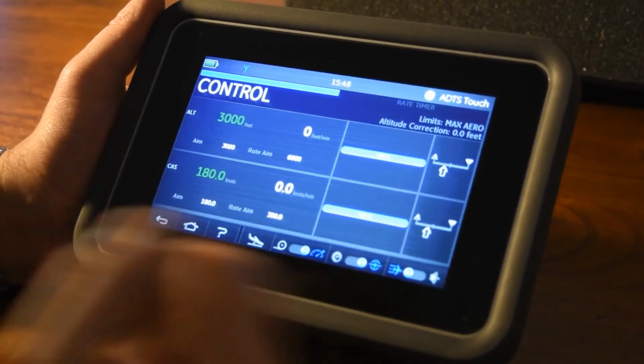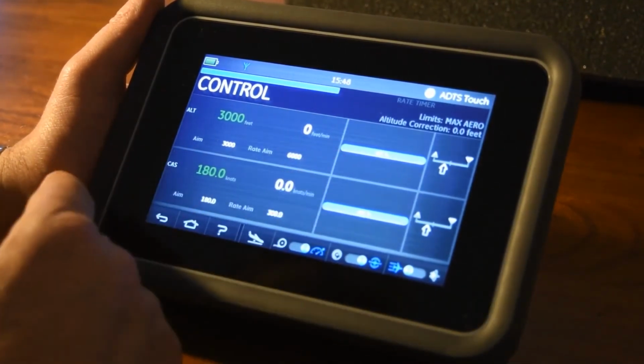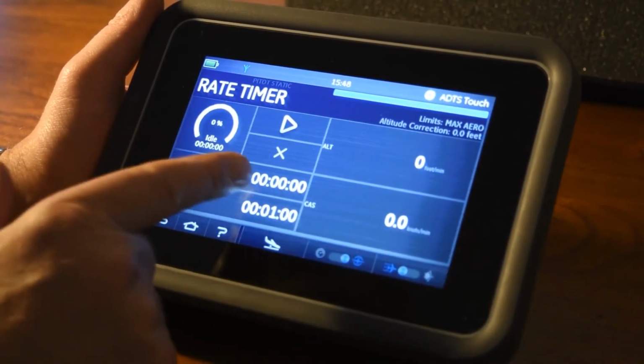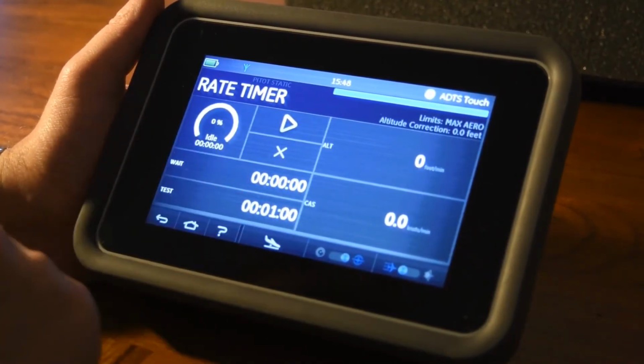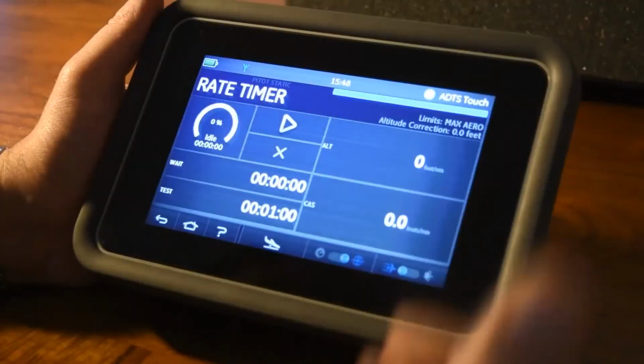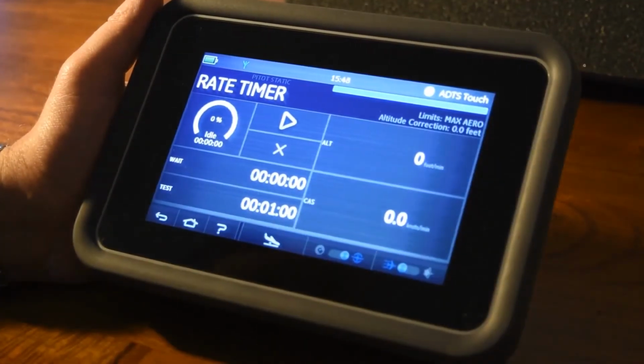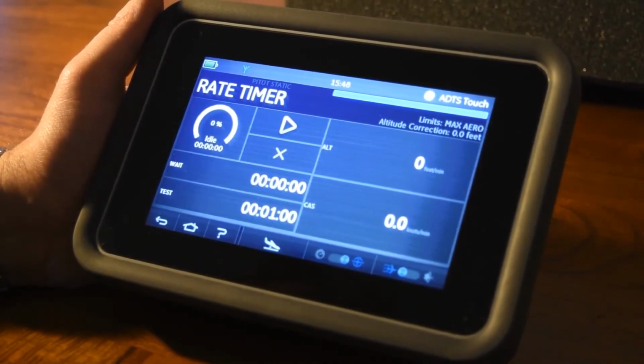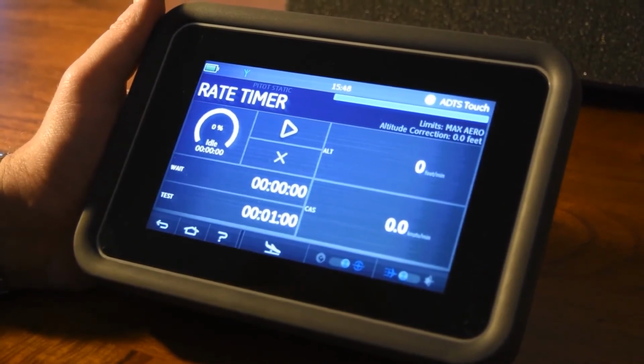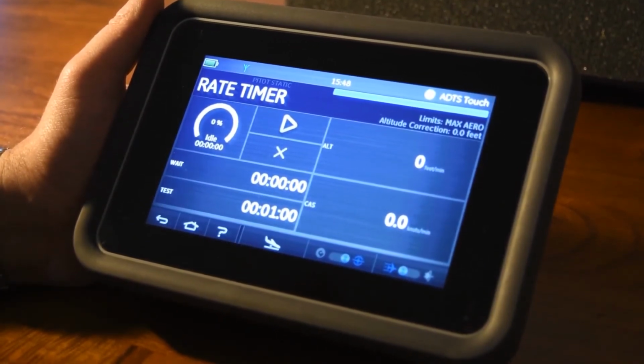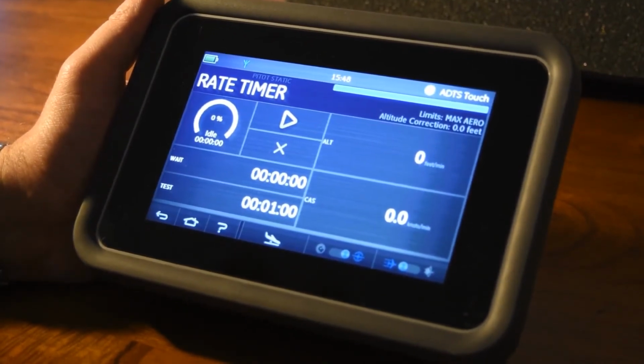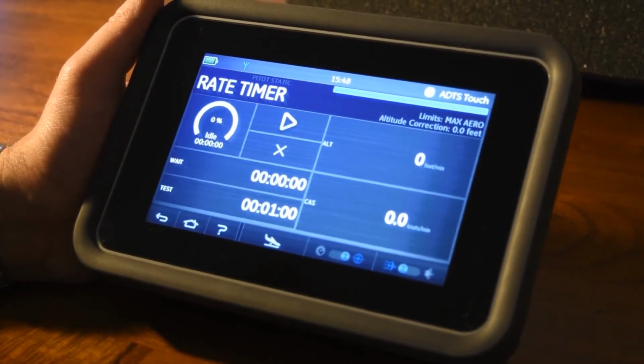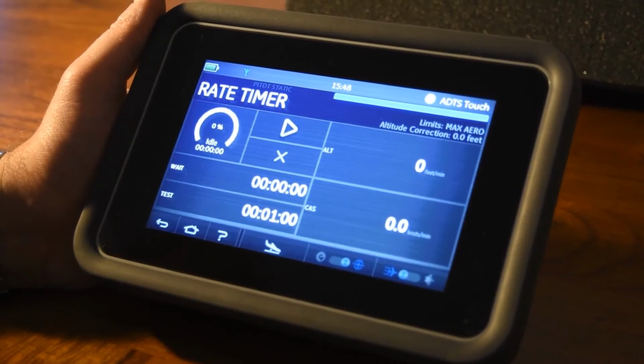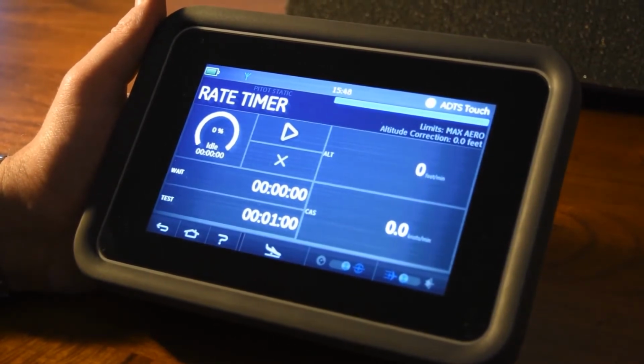In order to do that, we would go over and do a leak test. I'll set the leak test up first. In the leak test we have a wait time and we have a test time. The wait is because when we're changing pressures, changes of temperature are going to cause variations in pressure as that temperature stabilizes. So we have a wait time to overcome what we call the adiabatic effect. And then test time is how long you require to test for that leak. So you can come out and say, look, it's better than 100 feet in 1,000 feet. I think that's a light aircraft spec.